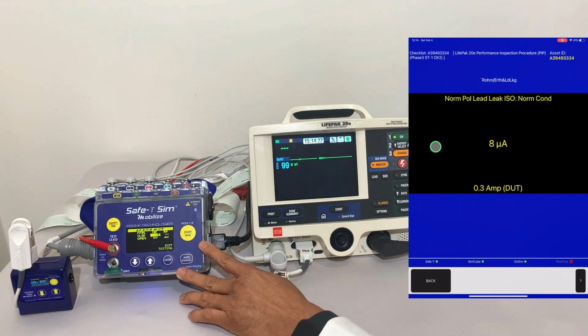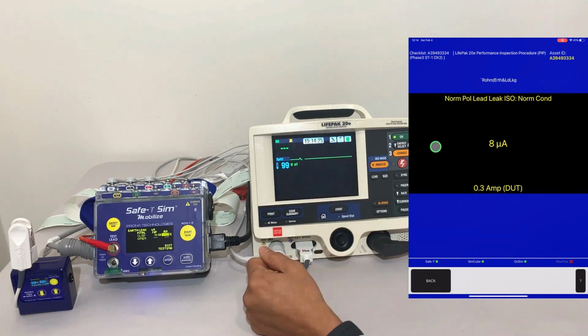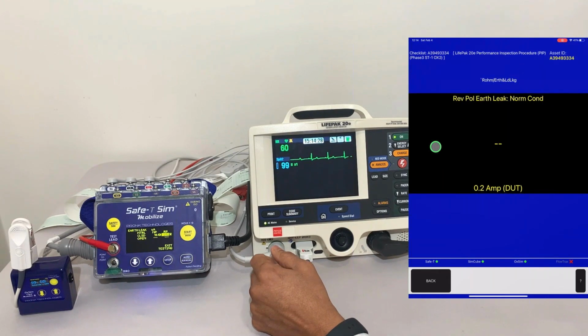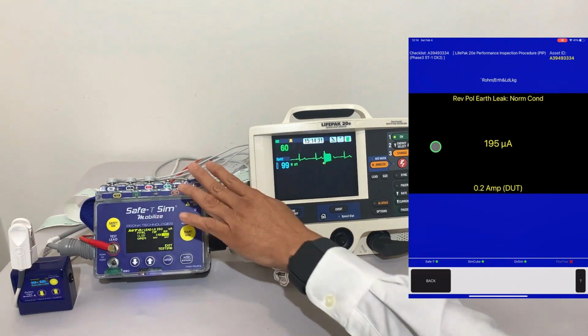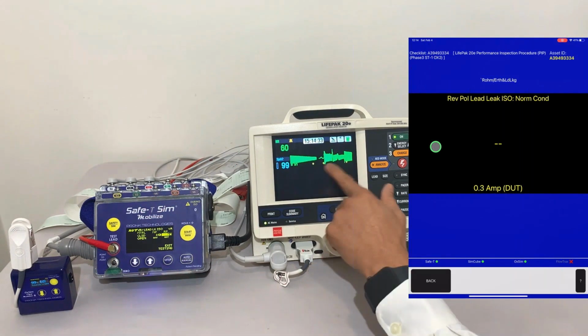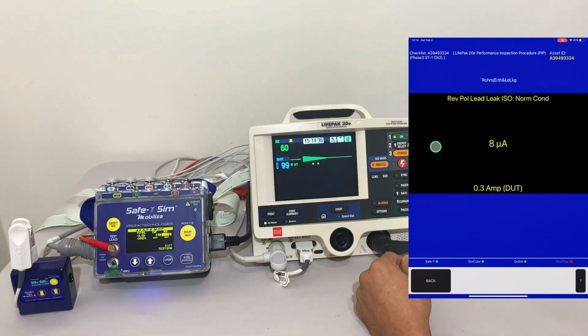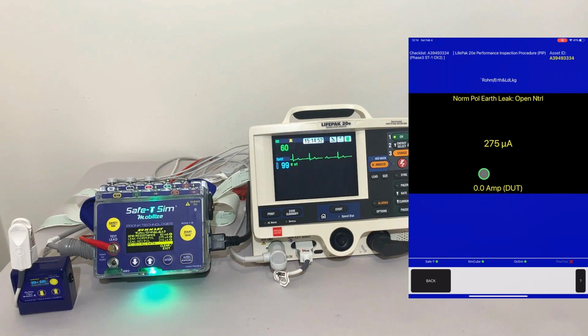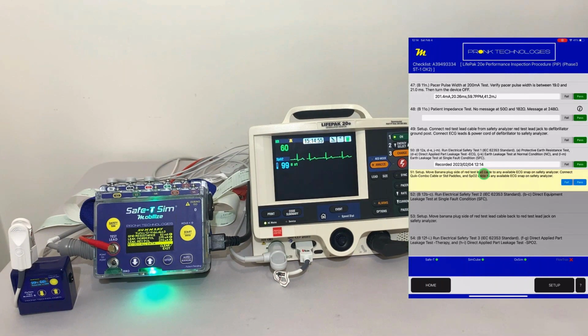And you can see when it's doing the leakage test, you could see some noise here. That's normal because we're doing a mains on applied parts test where we're taking AC voltage and actually applying it to the leads to measure leakage. So normally you see some noise on the ECG signal as well. You can see here on our app, it's performing the test. It's telling you the test that's being performed, the measured leakage, and how much current the device under test is drawing. So we're not drawing too much current here. It's going to complete the test, automatically post whether all of those tests passed or failed, and record the date and time we did those tests.